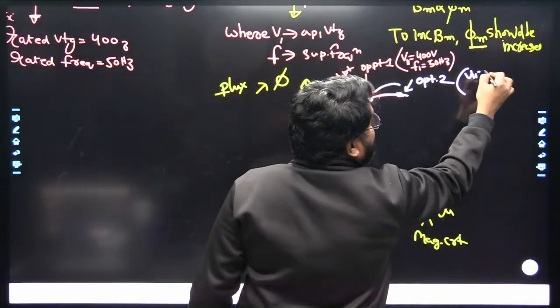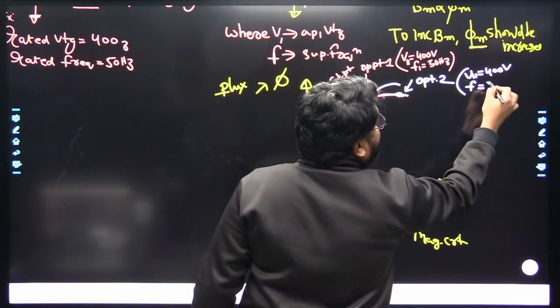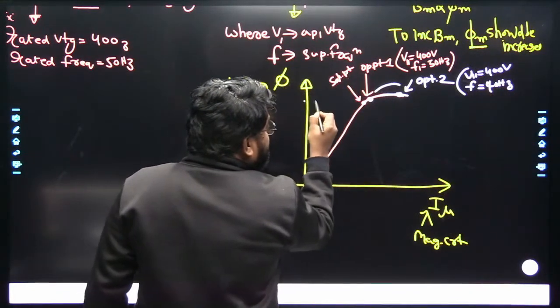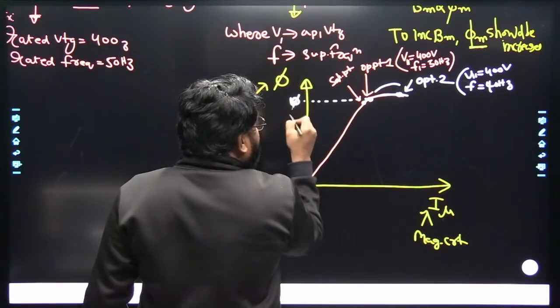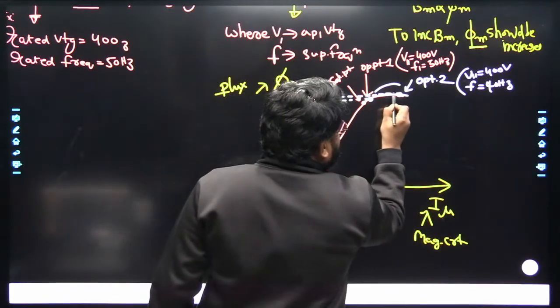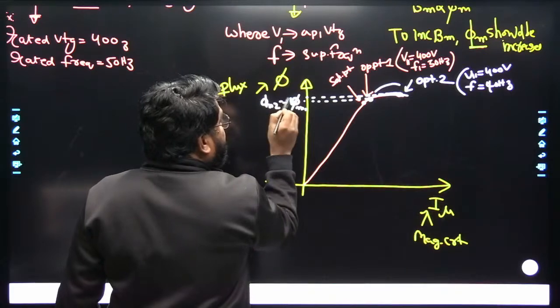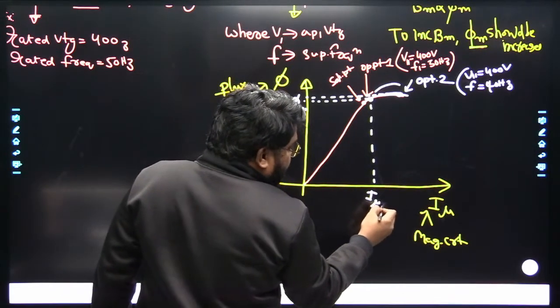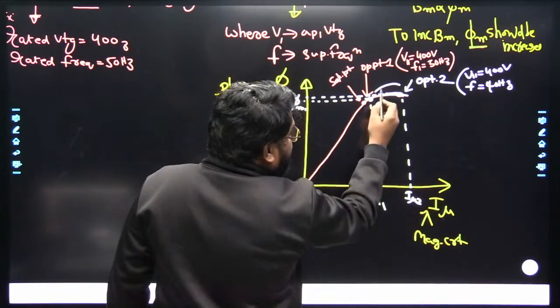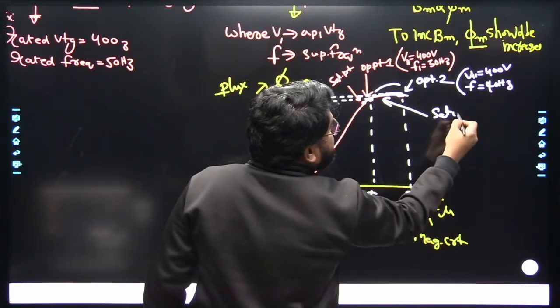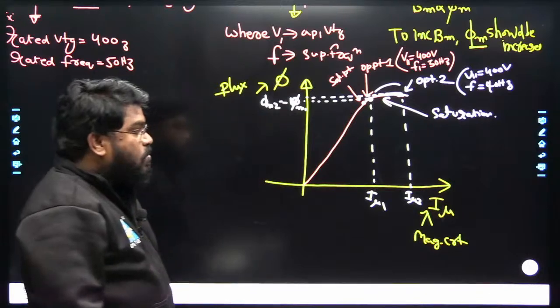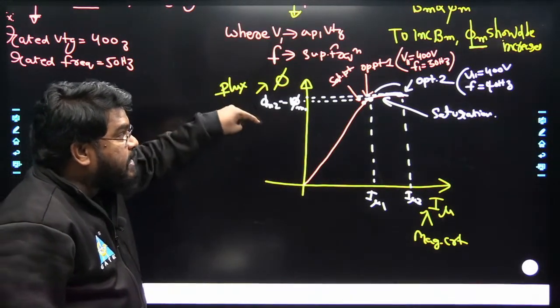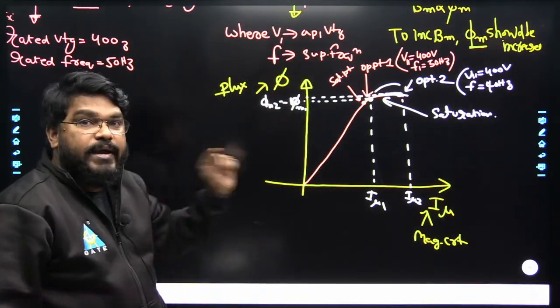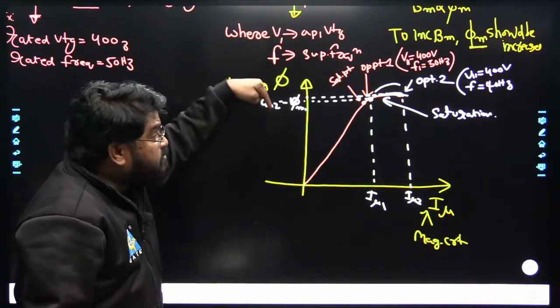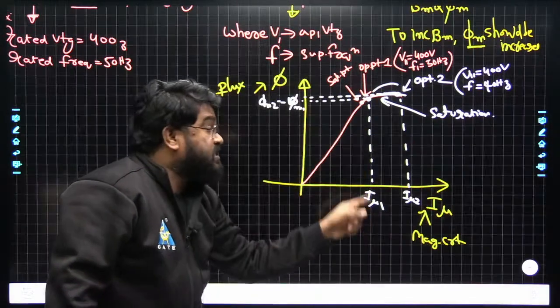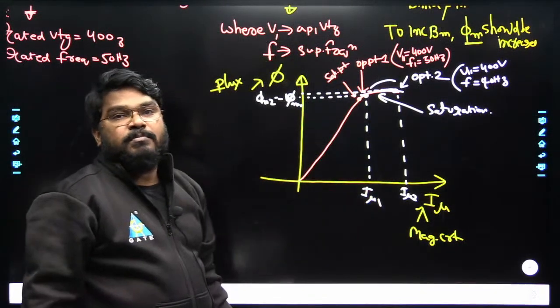Now this is operating point 2, at this condition V1 is equal to 400 volts and frequency is 40 Hertz. Compare here: this is phi maximum 1, and this is phi maximum 2, almost equal. This is I-mu 1 and this is I-mu 2. This region is known as the saturation region. So what we conclude is that in order to increase the flux in the saturation region, the transformer core goes into deep saturation, which demands high magnetizing current in the transformer. Is this point clear?